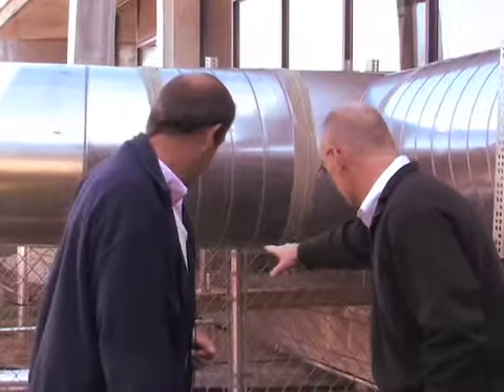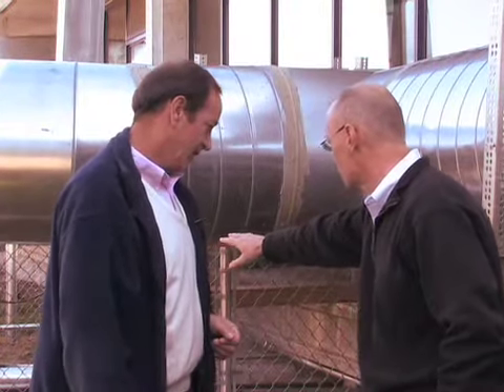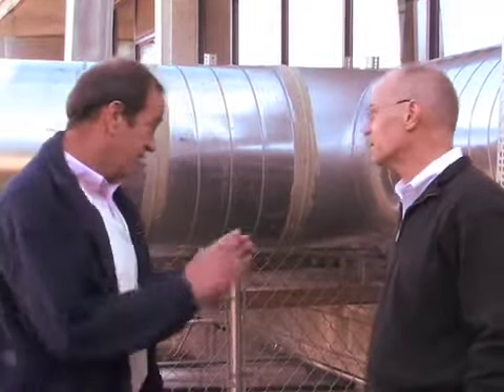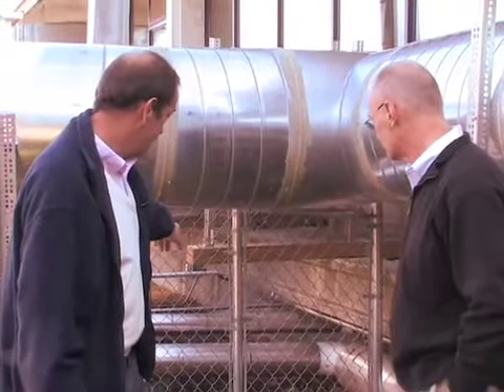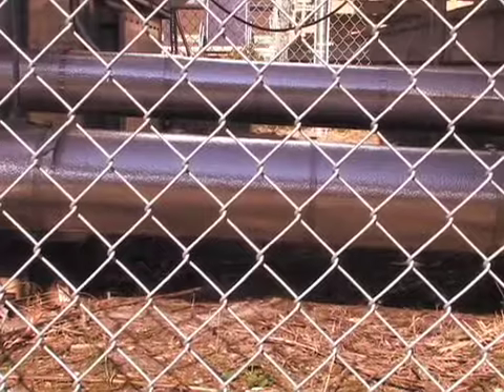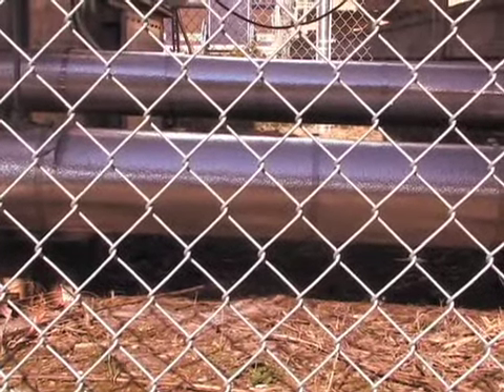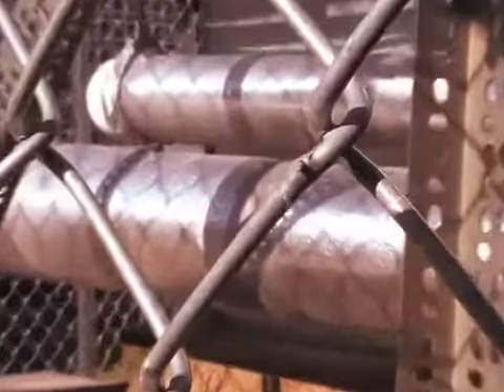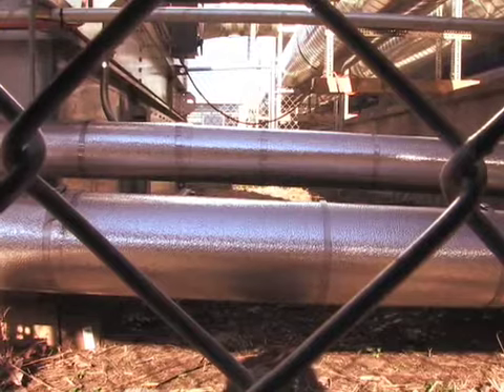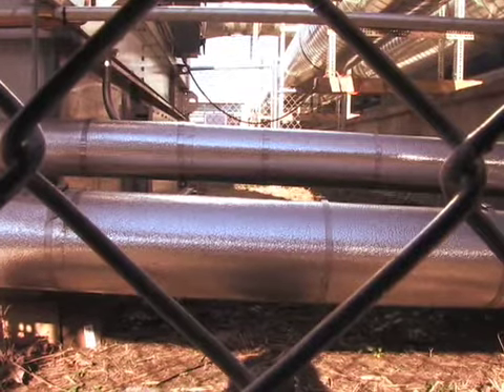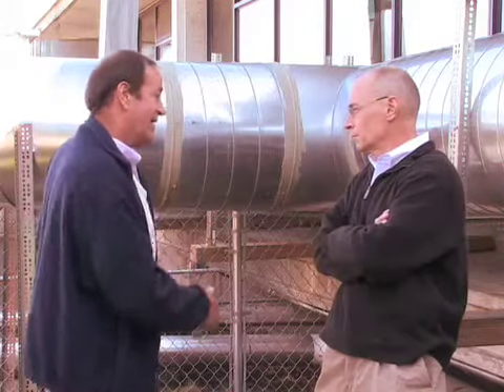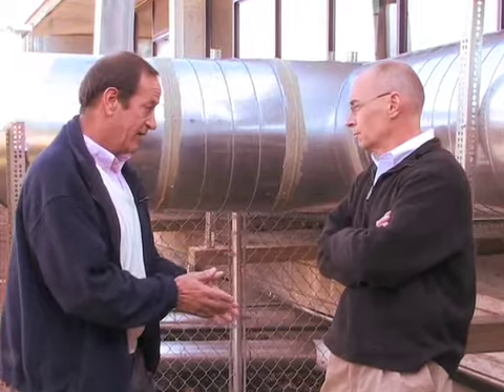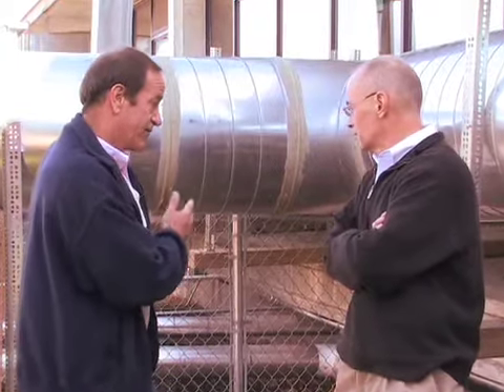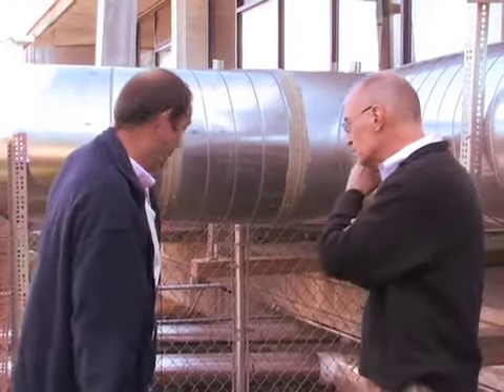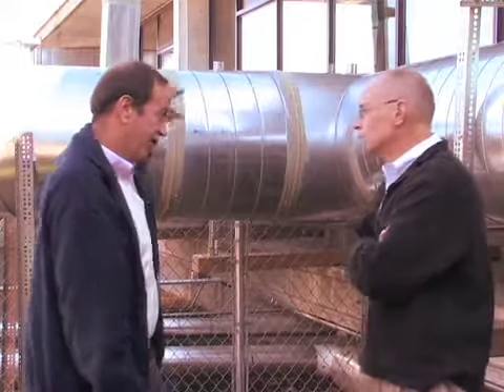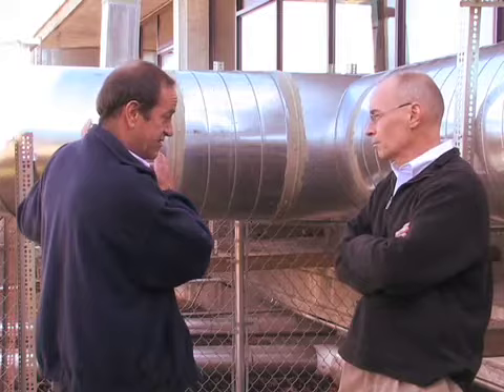And what about all these pipes running down here? It's temporary, where would those be in a permanent design? Those would be inside the building. That's a very good point. Those two pipes you see behind us, one is the steam feed, the lower pipe, and the top pipe is the condensate return. Now, if you understand New England winters, it gets very cold during the months of January, February, basically sub-zero. As our boilers cycle in this building, when the building is satisfied, the boilers will shut off. At that point, any steam in the system condenses the moisture. The problem we have with these temporary units is that they literally freeze. We do have heat trace tape on the condensate returns, but that's not up in the valves. The valves freeze, so when the boilers come back on, these things are no longer operating until we get here and thaw them out.